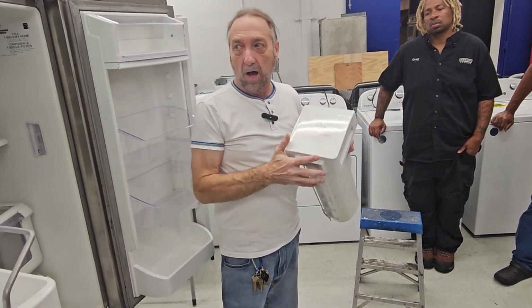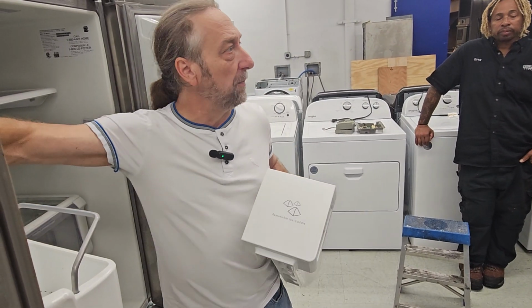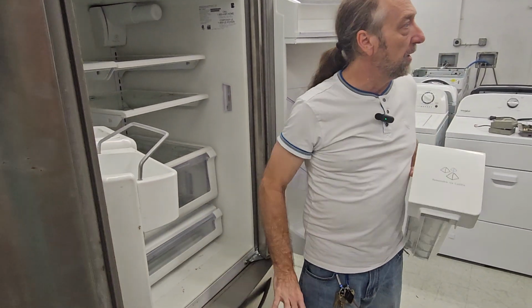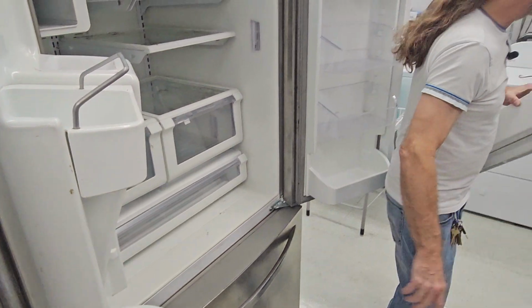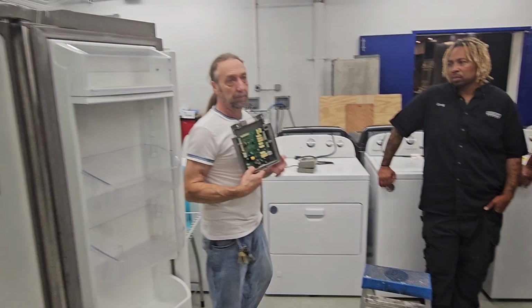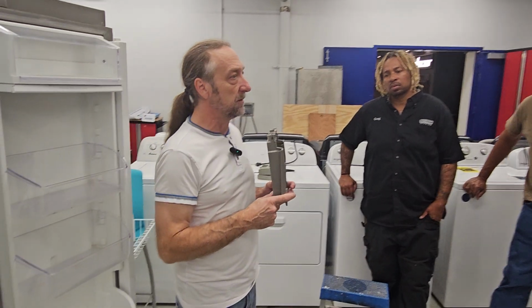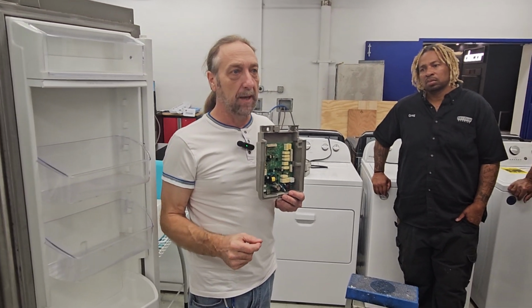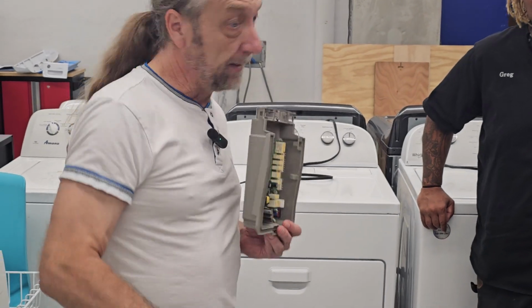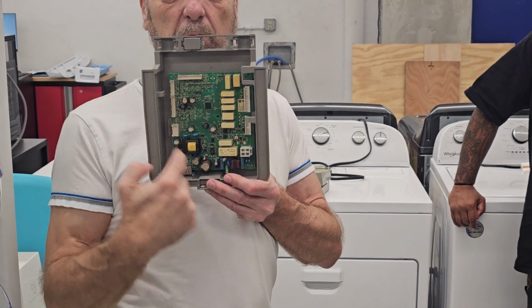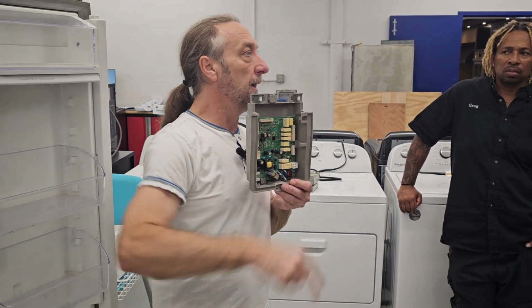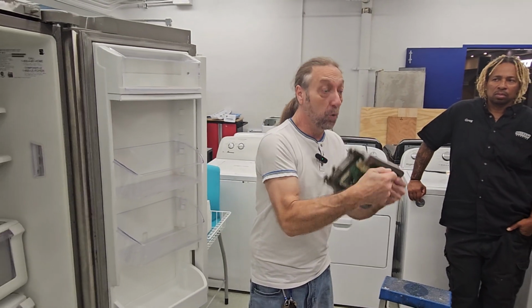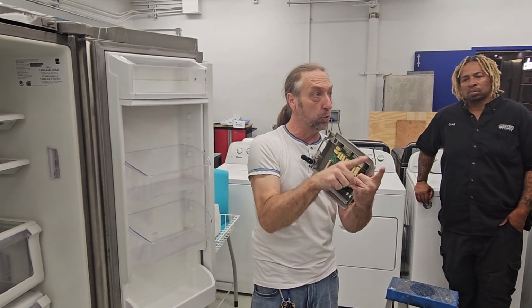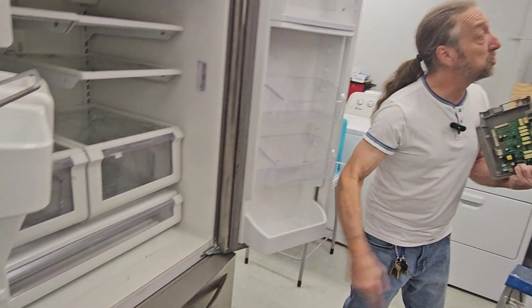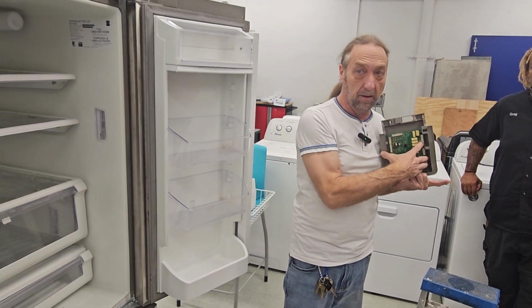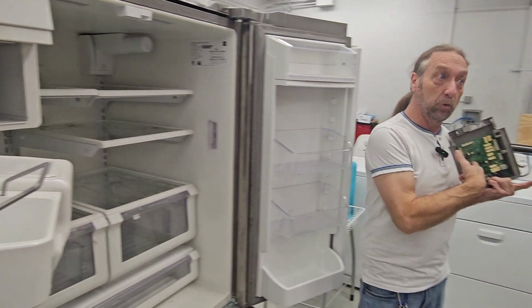So all of these components, the lights, the ice maker, the sensors, the damper, the fan motors, the compressor, they all run back to this board. When you're doing the hands-on, use the diagram and try to figure out, okay, the evaporator fan motor is in the freezer, but where does it connect to the board? What two wires on this board go to that fan motor? Check the wires, not the board. Unplug it, see which two cables go to the fan, and check the fan from the board. I want to check the crush-cube solenoid, can I do it from the board? Yeah.